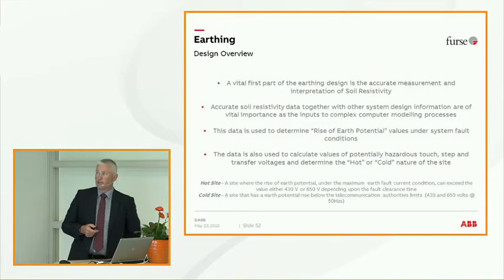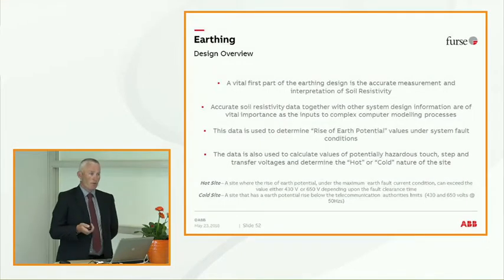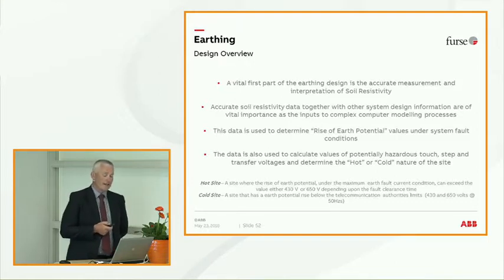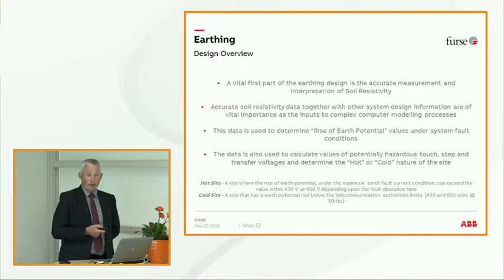We get involved with earthing design as an organisation, and like we're part of ABB now, it's a service we can offer. I've mentioned it's an accurate measurement of the soil resistivity. Touched on areas of soil resistivity, that's important for earthing design. If you've got a system that needs safe working conditions, then this needs to be critical. We need that soil resistivity data accurately, then we can put that into software that will give us the modelling. We can work out the rise of earth potential, and we can also ensure hot and cold sites to make sure that it's safe to work.